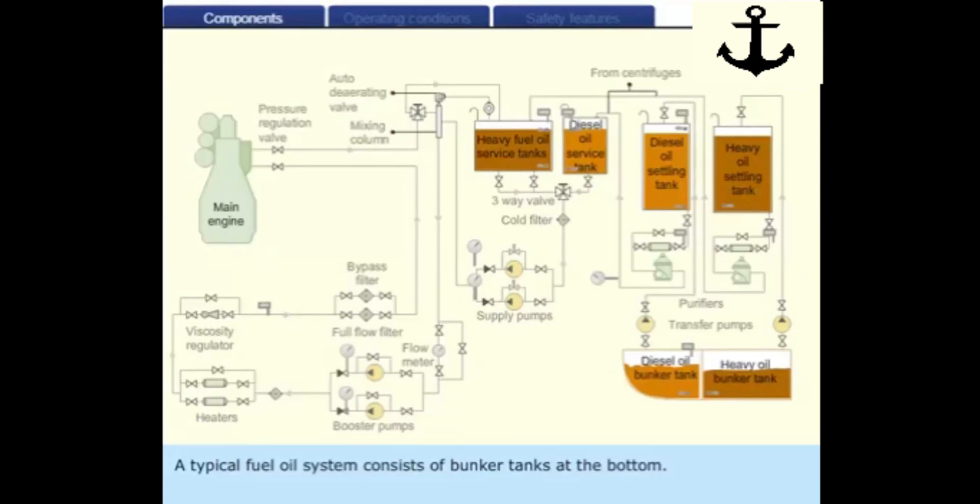A typical fuel oil system consists of bunker tanks at the bottom. They can be double bottom tanks or wing tanks into which the oil is bunkered. The transfer pumps transfer the fuel oil from bunker tanks to settling tanks where water is separated from the oil.